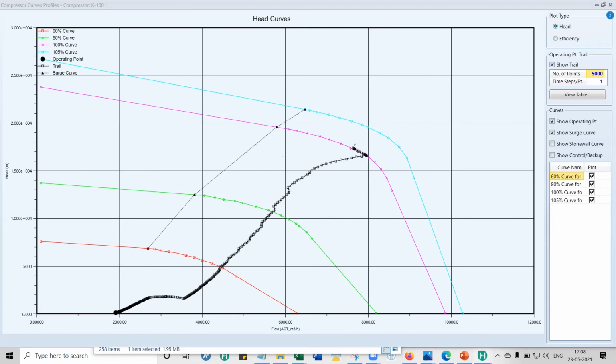See, the moment it is moving like this, these oscillations, this is forward and reverse flow. This is what is happening, forward and reverse flow. So there is fluid flowing out of the compressor, entering into the compressor, flowing out of the compressor, flowing back into the compressor, flowing out, flowing in, flowing out. So the fluid is oscillating inside the piping. It is moving forward, going back inside, moving forward, going back inside. Okay, understood.